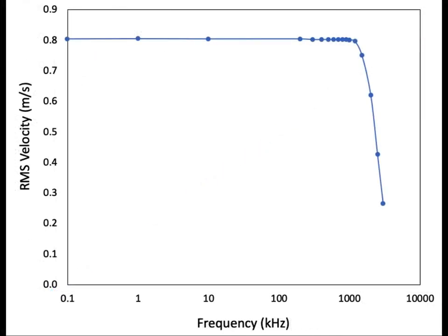This plot shows a result of using frequency modulation to simulate the shaker. The most interesting result here is that we can not only calibrate the LDV as a function of frequency, but we can also characterize the bandwidth of the LDV as well.